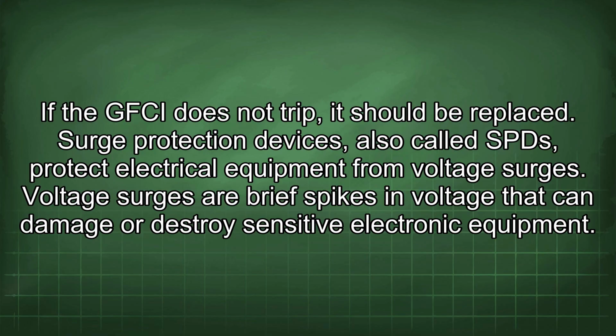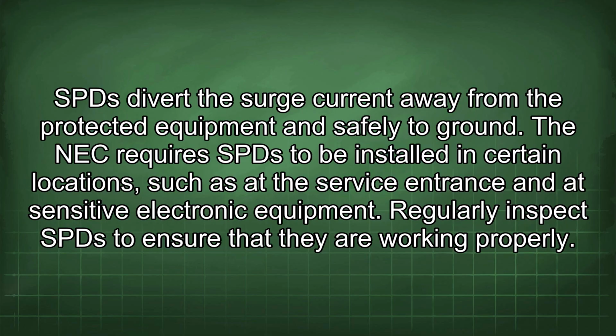Surge protection devices, also called SPD, protect electrical equipment from voltage surges. Voltage surges are brief spikes in voltage that can damage or destroy sensitive electronic equipment. SPD divert the surge current away from the protected equipment and safely to ground. The NEC requires SPD to be installed in certain locations, such as at the service entrance and at sensitive electronic equipment. Regularly inspect SPD to ensure that they are working properly.